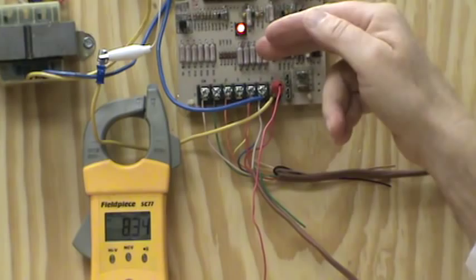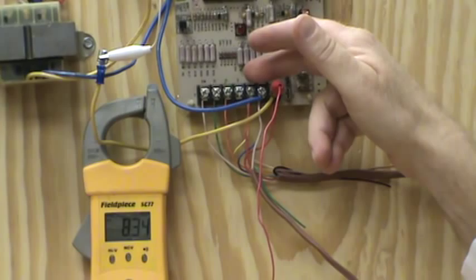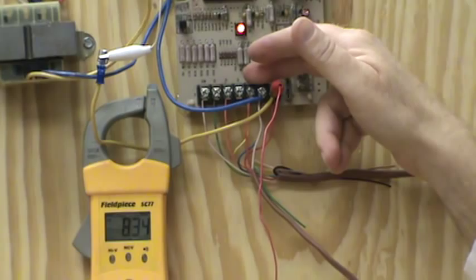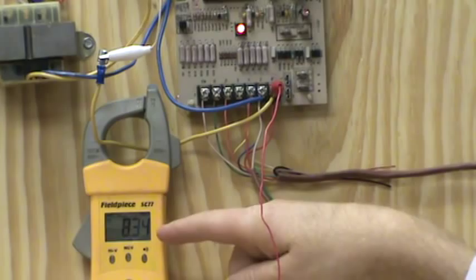Now, when you do this, you can hit the branch circuits, and when you hit that one branch circuit, in this case the cooling circuit had the high amperage. Each time you do that, it does damage to the transformer and all the circuits. You can see how that's got some high amperage, 8.34.